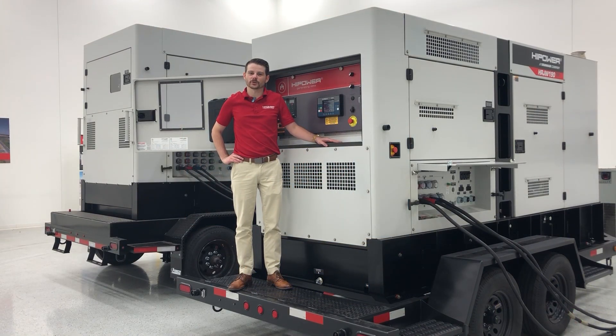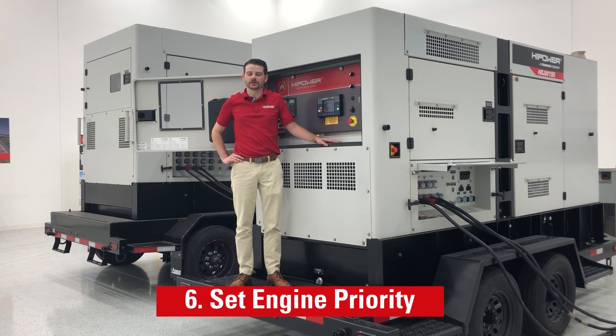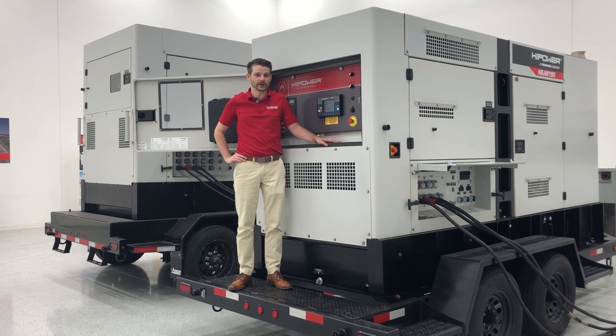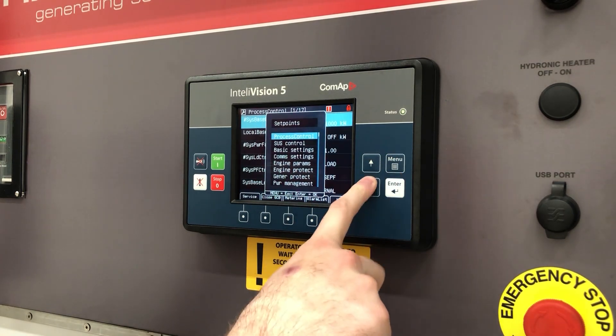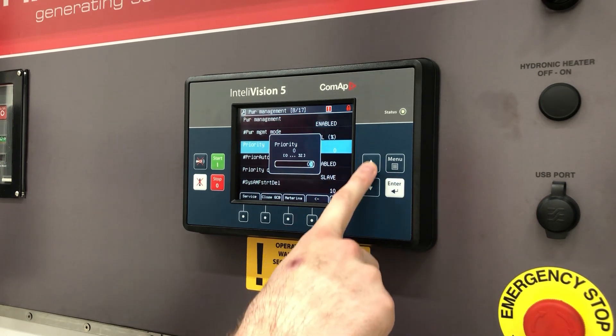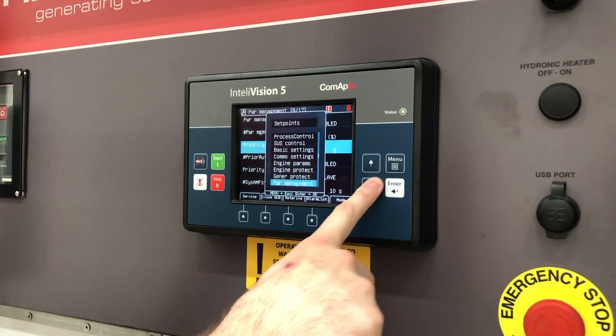Another feature of our ComAp controllers is the engine priority. This will help determine the operation of the units in the paralleling system. It will determine which units and how many units run at a given time, or if all the units are to run simultaneously and share the load equally. To change the engine priority, click menu and go to set points. Scroll down to power management and here you will see the priority set point. This set point is displayed on page 12 of the IV5 controller.